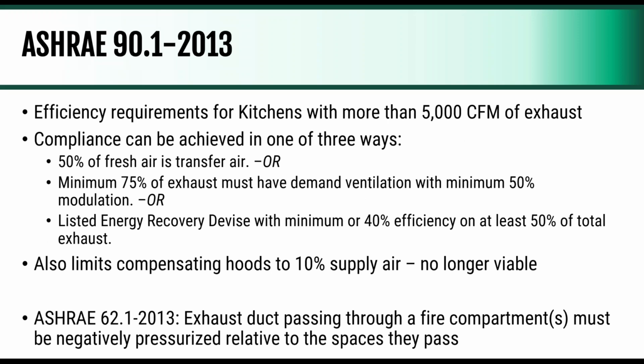ASHRAE 90.1 version 2013. This is what we call demand control. It's the statute, but basically it says any kitchen that has over 5,000 cubic feet per minute of exhaust needs to be compliant with ASHRAE 90.1, and that can be achieved in one of three ways. 50% of the fresh air is transfer air, so this is typically only useful in kitchens with very open concepts. The one thing we do see that actually can meet this a lot is grocery stores, where they have a kitchen operation where they're cooking take-home food.